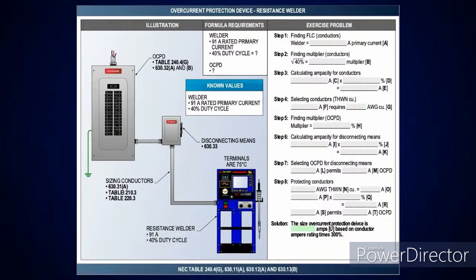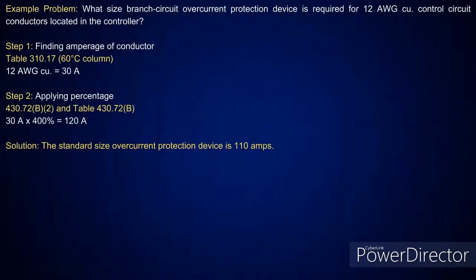Now look at here. That's a good looking resistance welder they did there. I tell you, they put a lot of detail in these illustrations. And I'll tell you, when you throw it up on a big screen, they look even better, because you see the detail that's in them. They blow them up and put the text in there just like you would see on a regular unit. So they really do their work good. And then this one here, I've got a 91 amp resistance welder with a 40% duty cycle. So you're going to look and get your amperage first, and then you're going to get your duty cycle and then work down based on the conductors in that 300%. And that way you'll know if you sized it correctly or not.